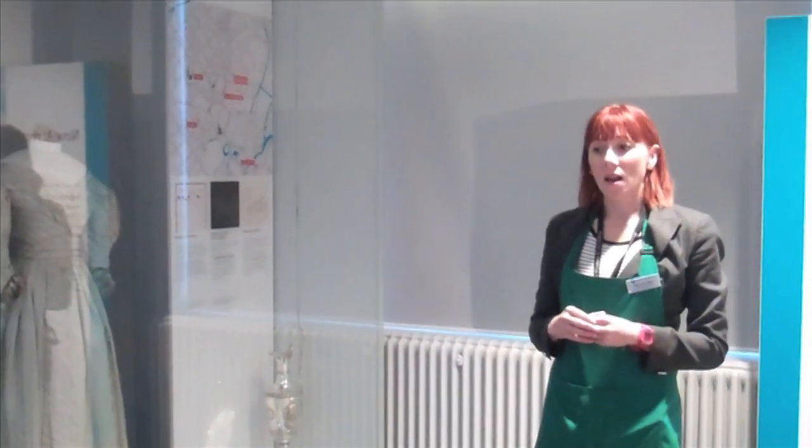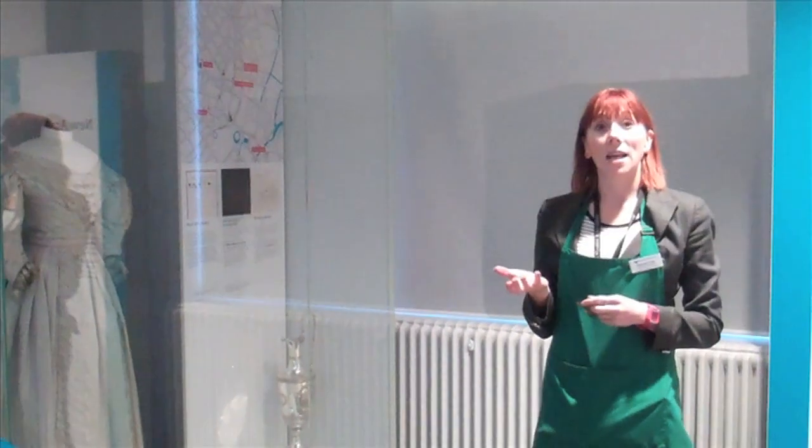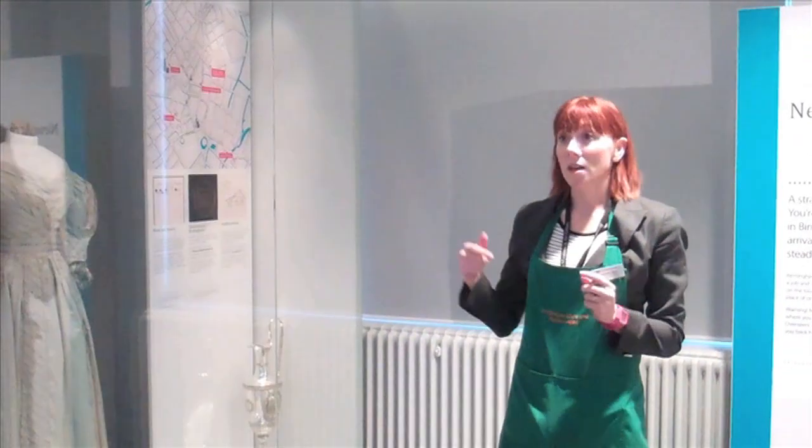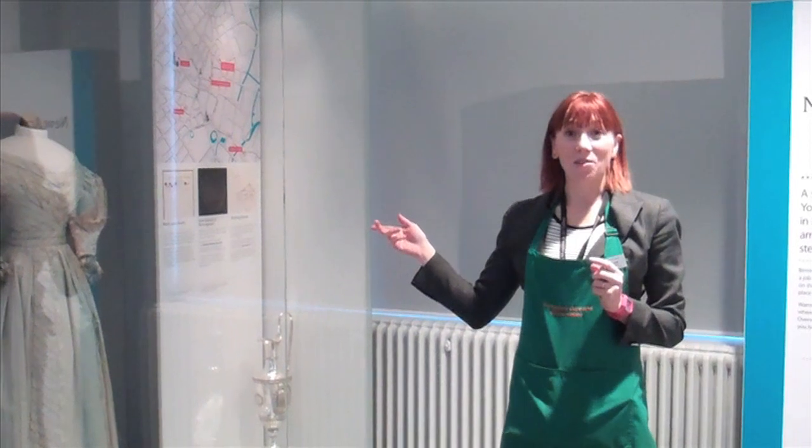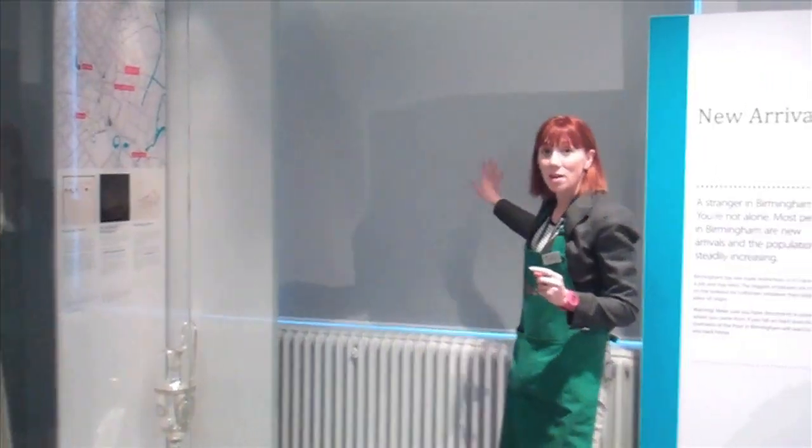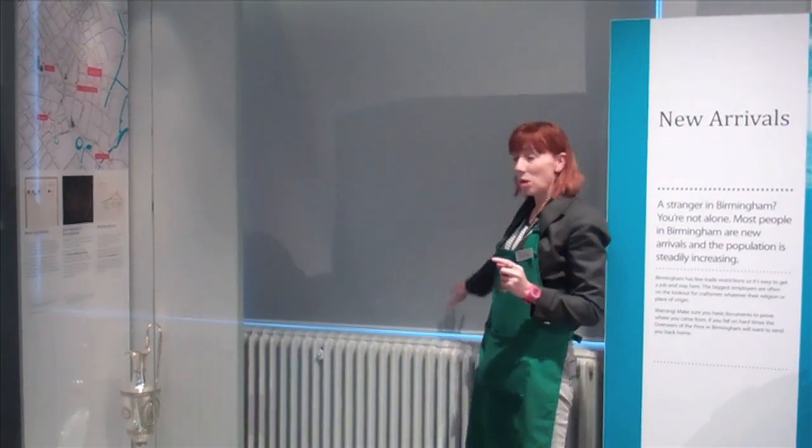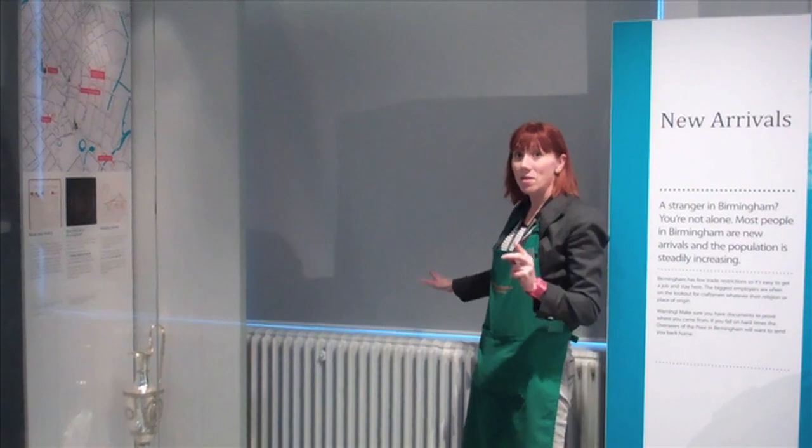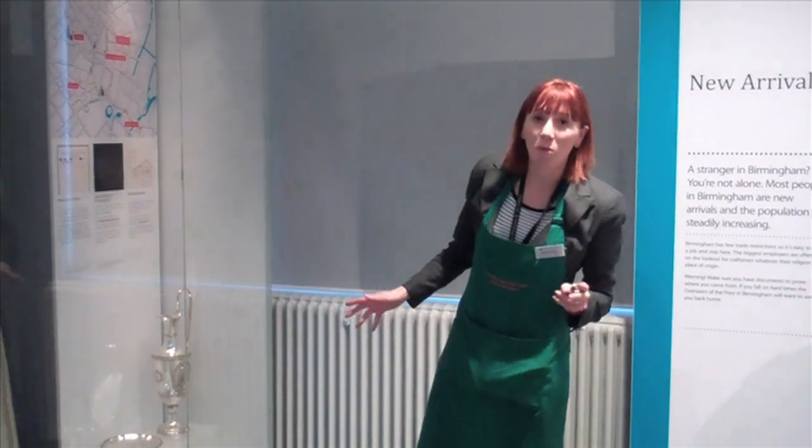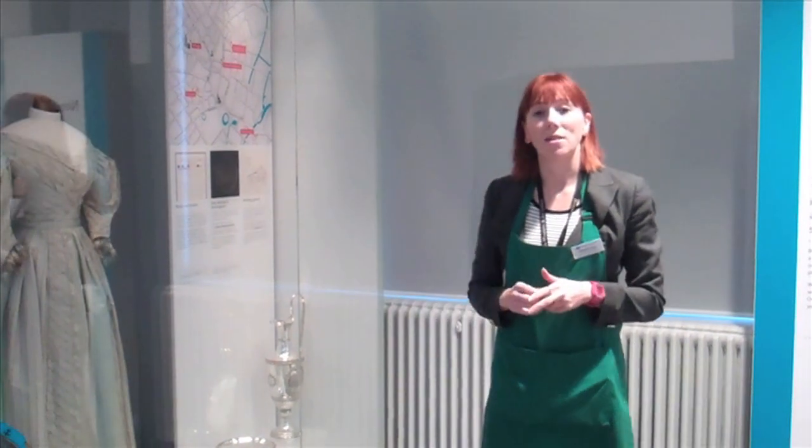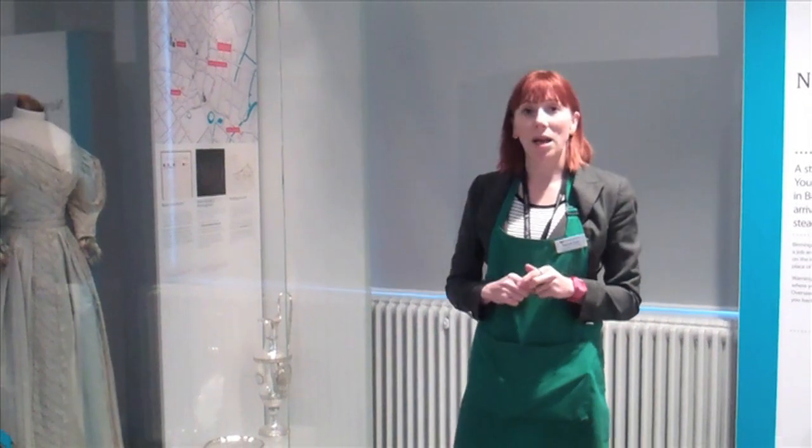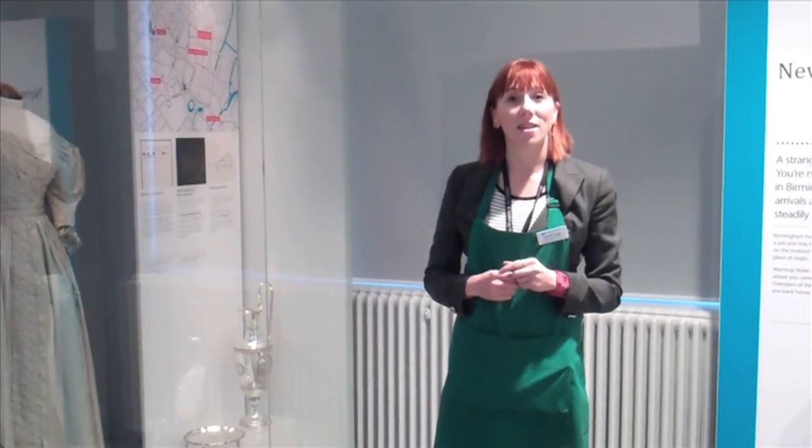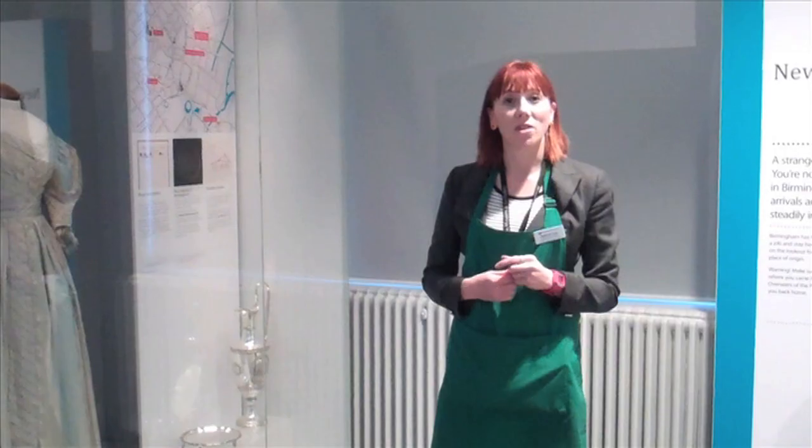So Rose and I have checked the light levels in the gallery. There's no UV. We've checked the light levels in the case. There's no UV. We've checked the light levels by the window which has the blind kept down. There's no UV. We've got the problem with the calibration of the logger so we'll take that back to the office, sort it out and get it back in the showcase so we can get the correct data for our monitoring.